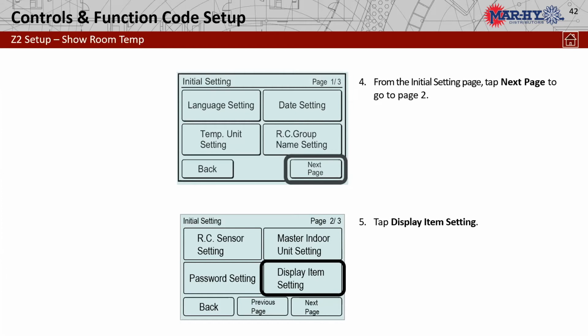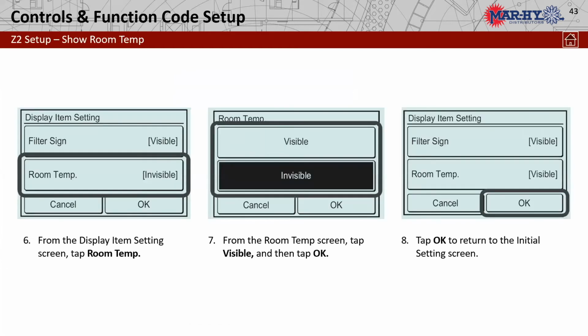And if we were to push the submenu within the submenu on display settings, we go ahead and tap that. And basically what this is, do you want your filter sign visible on the thermostat and the room temp as well? Yes, make those visible. I don't know why they put invisible, but make them visible so they can be seen from the main thermostat. It'll tell us when the filters are ready to be changed, and this will give us an actual room temp display on the thermostat itself.